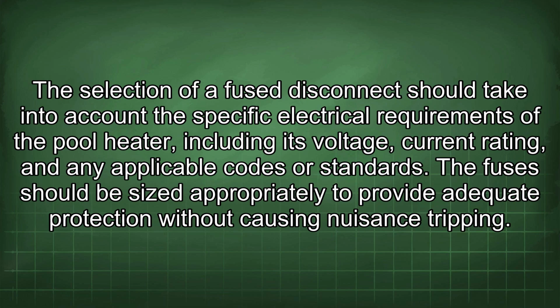The selection of a fused disconnect should take into account the specific electrical requirements of the pool heater, including its voltage, current rating, and any applicable codes or standards. The fuses should be sized appropriately to provide adequate protection without causing nuisance tripping.